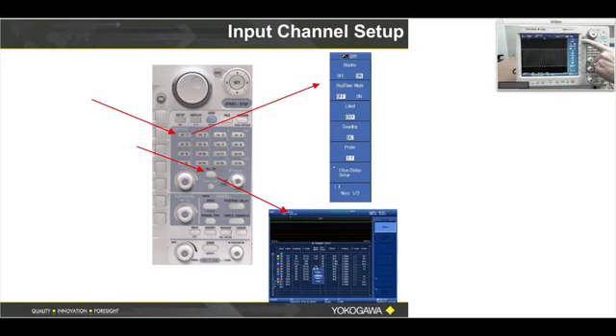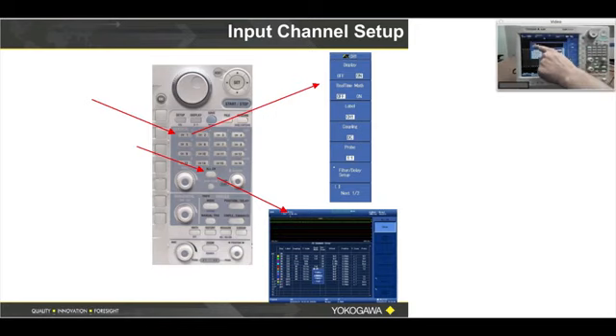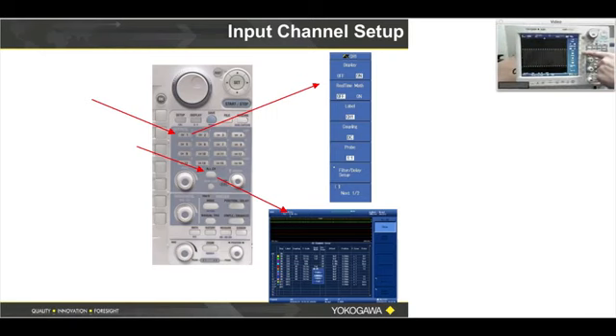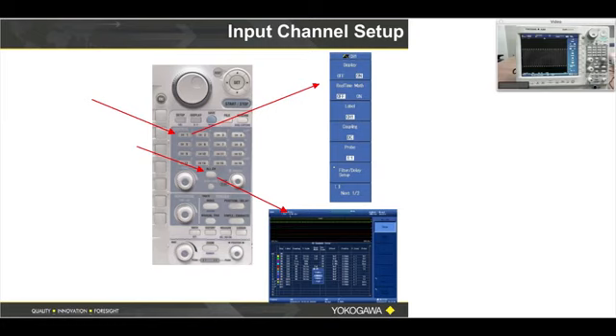Please look at soft menu items one through seven — these are very similar for all modules and all channels. I can turn the display on or off, I can label the channel — there's a place to put the word 'pressure,' for example. At soft menu button number four you can press DC, AC coupling, or ground, which is traditional with an oscilloscope or recorder. I can set the probe coupling — in my case I have the blue 10-to-1 iso-probe, so I have 10-to-1 on my probe.